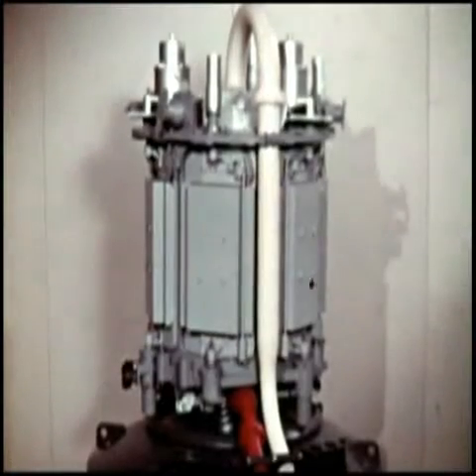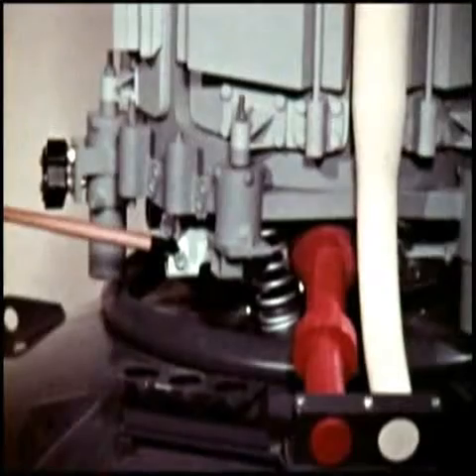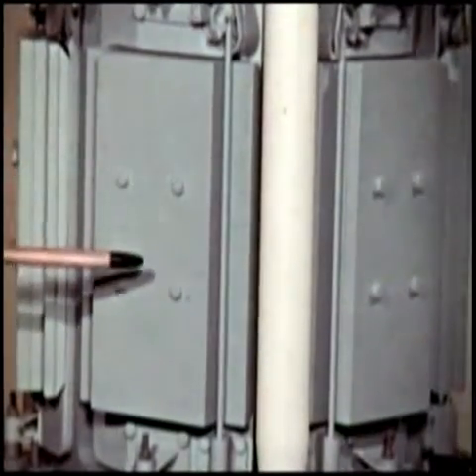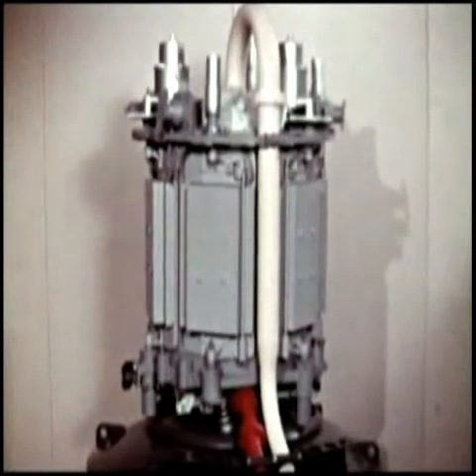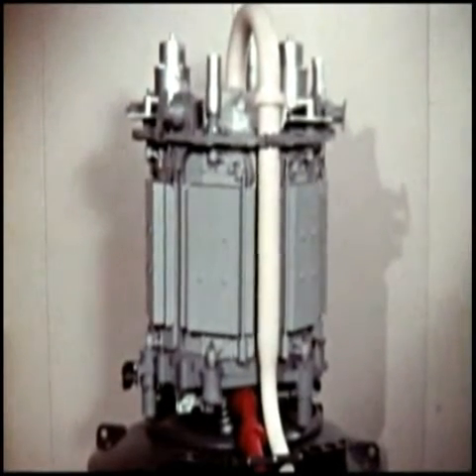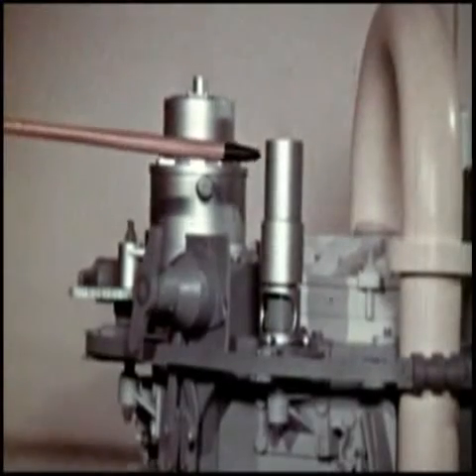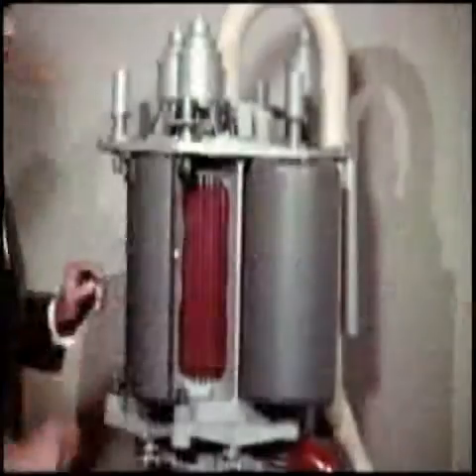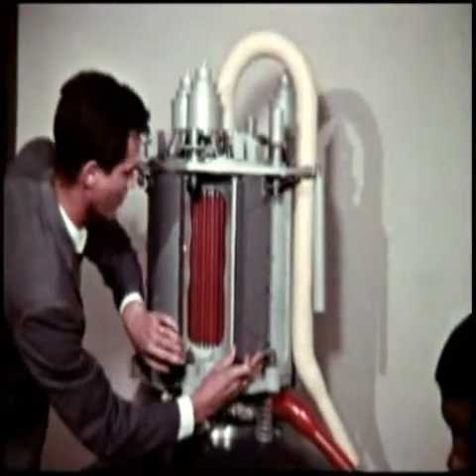The reflector assembly is supported on brackets affixed to the base of the core vessel. The brackets support 6 fixed beryllium strips and 6 rotatable beryllium control drums. These are alternately arranged around the core vessel circumference, forming, when the drums are in, a continuous 3-inch thick external reflector. The control drums are actuated by electromechanical drive systems. By rotating the drums, the neutron leakage from the core is modulated, thus controlling the power output of the reactor.